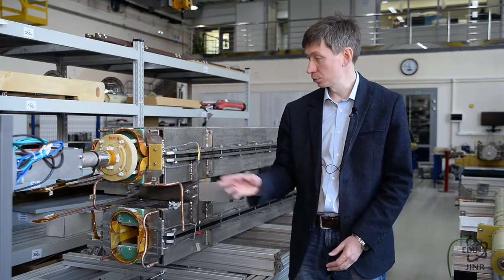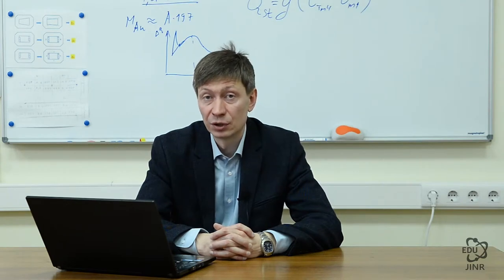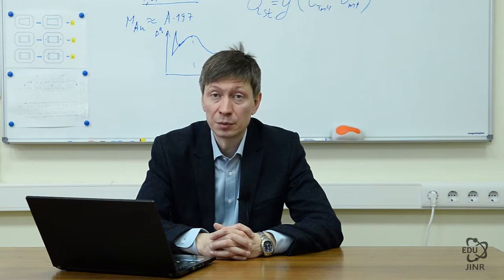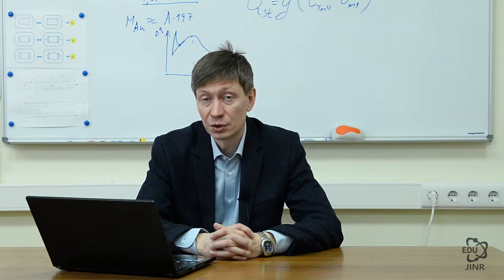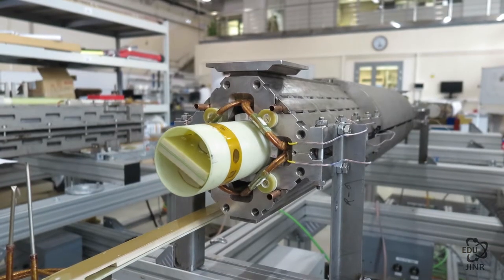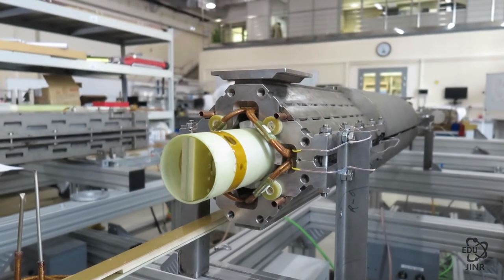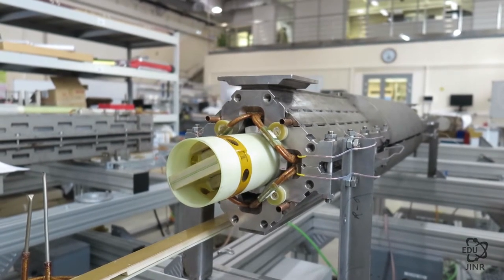The sensor used to measure the system of rotating coils is exactly the same as the one that will be used in the cryostat at the cryogenic testing stand. There are several basic ways to measure a magnetic field in circular accelerator magnets, all of which have been highly developed and well detailed in technical literature. For the Nuclotron-type magnets, we use the rotating harmonic coil method, where the coils of a certain configuration rotate inside the working magnet aperture, and a special EMF signal is analyzed which is induced in these coils during rotation.